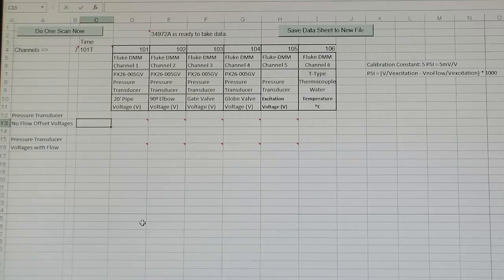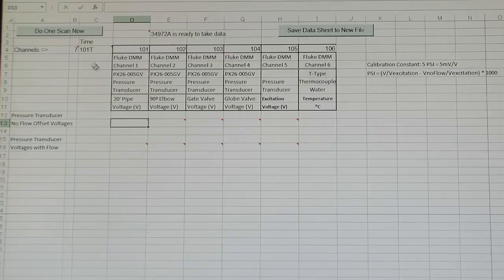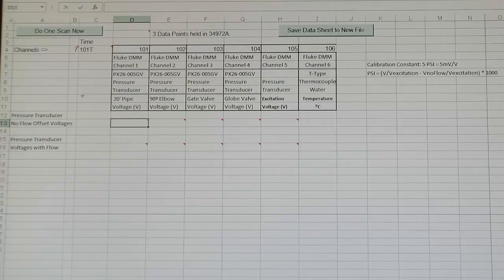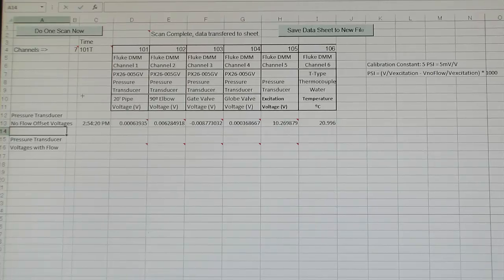To start off, we will record the no flow offset levels of the pressure transducers. To do this, highlight cell D13 in the Data tab. With no flow going through the pipe, press the Do 1 Scan Now button. The computer is going to read the pressure transducer offset voltages and place them into the spreadsheet.